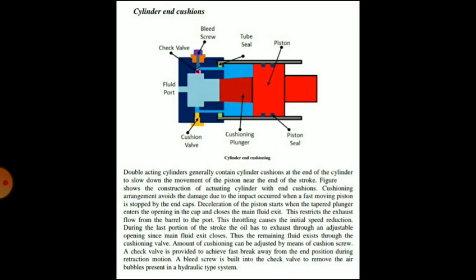Cylinder end cushions: double acting cylinders generally contain cylinder cushions at the end to slow down the movement of the piston near the end of the stroke. The cushioning arrangement avoids damage due to impact when a fast-moving piston is stopped by the end caps. In the diagram, you can see the piston and at the back side of the piston there is a cushioning plunger.